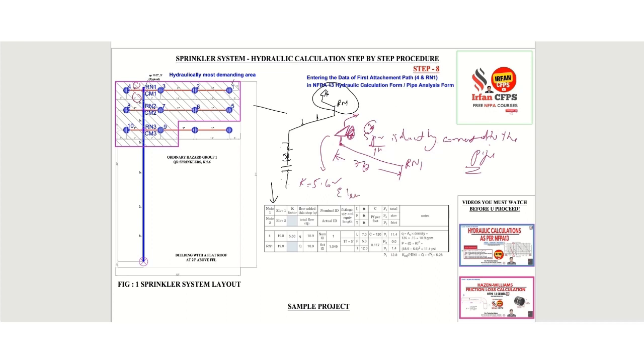We already know the K factor of the sprinkler is 5.6. The branch line elevation is 16 feet from finished floor level. The flow Q from one sprinkler equals area times density: area is 126 square feet, density for ordinary hazard group 1 is 0.15 gpm/sq ft, so the flow from this sprinkler will be 18.9 gpm.